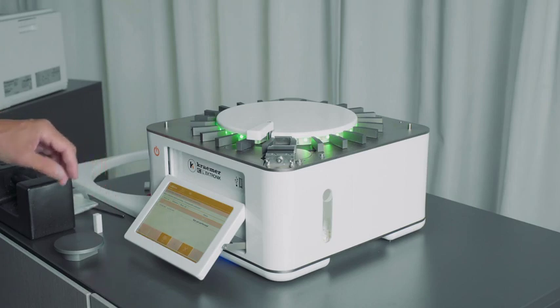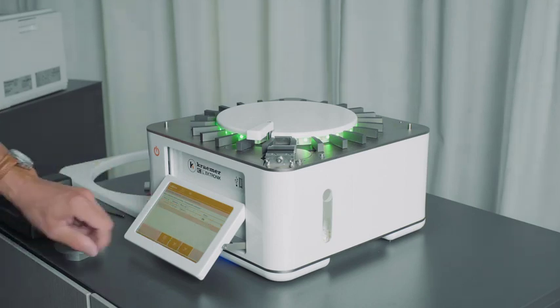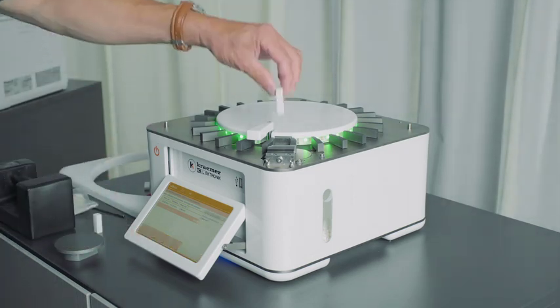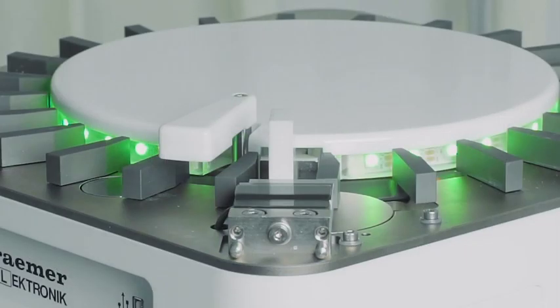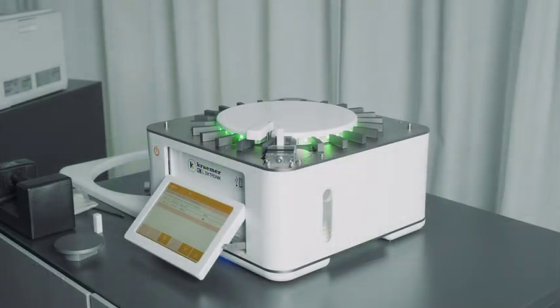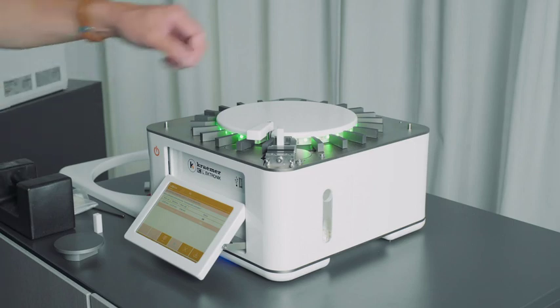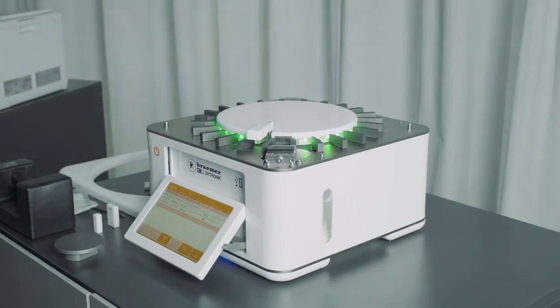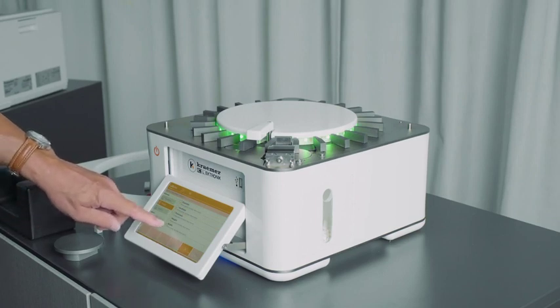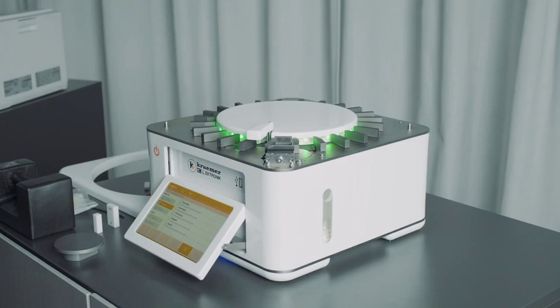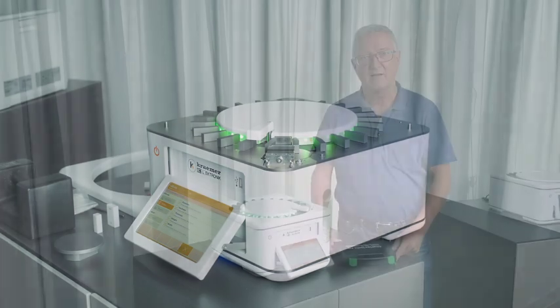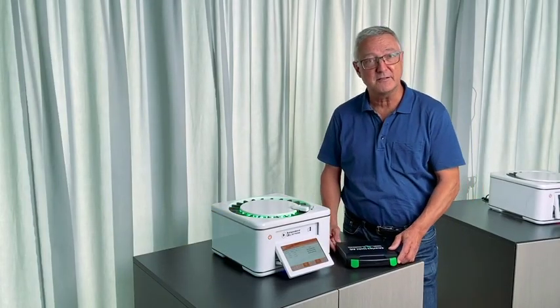We remove the gauge and we go on and select 20 millimeters, second calibration point, and we enter the 20 millimeter gauge block. Also here we have 19.99 as a result. Status is OK. The accuracy of the diameter tester is fine. For this calibration, it is also possible to set up and pre-configure multiple points, like 3 points or 5 points, to verify according to your requirements. For the calibration of the width, it is measured in the same station, so it's the exact same procedure as for the diameter.